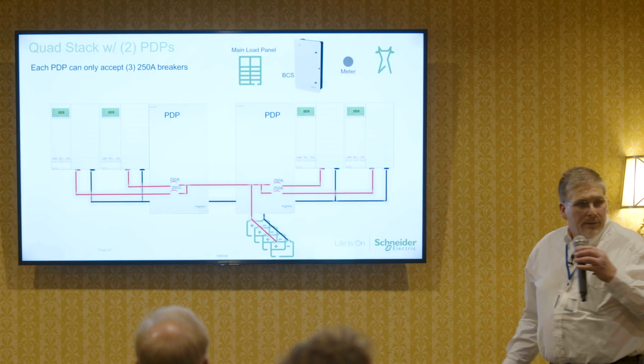So that picture, Eric, you are your AC input, you have an external ATS transfer switch if you are using grid as well as a generator? Yes, great question, Tom. So, yeah, we are using up the AC2 port. So if we are on grid with a generator, we still have to have an ATS upstream to select between one source or the other. But after that, it's just a matter of programming, right? So you're not selling back to the generator. And we can talk about that offline, but it's definitely doable with the platform.